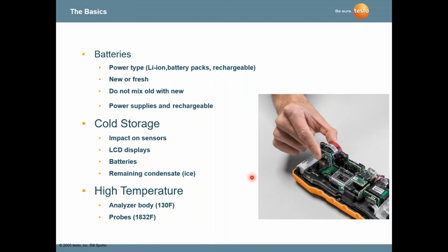Looking at the instruments themselves, most of them are powered by lithium-ion battery packs. This happens to be the inside of a Testo 300, and you'll see these are the sensors, which are replaceable in the field. Be careful with very cold temperatures, especially up north, because you don't want to freeze anything in the instrument. Freezing has an impact on the sensors, the LCD display, and certainly the batteries. If water isn't dumped out of the water trap, it could turn to ice and crack the trap, so make sure you keep it above 0 degrees Celsius. Below that, you get into extremely cold temperatures.